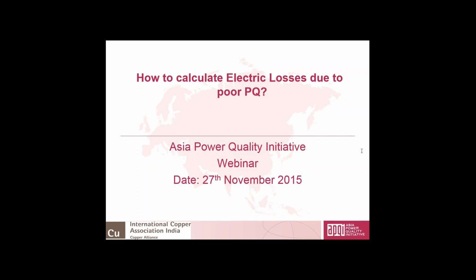Okay. Normally the voltage fluctuations may be because of two reasons. One is because of the supply system, and another is because of the load. So if we have a fluctuating kind of load, then we can have voltage fluctuations at the point of common coupling, which is experienced by other consumers. That is one reason. Another reason for voltage unbalance or voltage fluctuations may be typically from the supply system, which may be from the back of the supply system. If it is because of the load, by providing a shunt compensator, the voltage fluctuations also reduce. So it depends on which of these is causing the voltage fluctuations, whether it is because of the load or because of the supply.